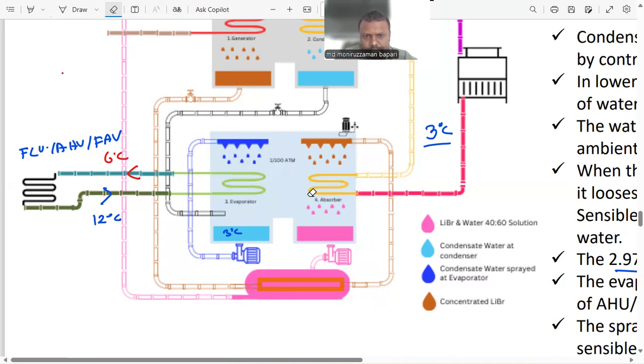To do so, remember at the generator, we have produced concentrated lithium bromide. This concentrated lithium bromide is to be sprayed here. And as lithium bromide is a highly hydrophilic substance, it's going to absorb the vapor and work as the absorbent, and it will turn into lithium bromide solution here. In this manner, the vapor is going to disappear from this chamber.